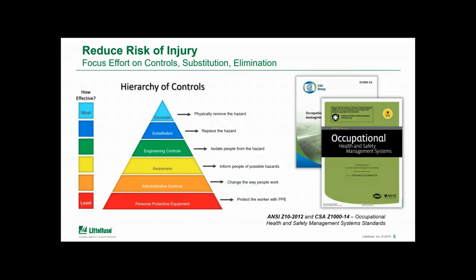Now, I do want to be clear that all those 3 items are critical, they're foundational blocks, and should be part of a safety strategy. But what we want to focus on are some of the more effective ways to make the workplaces safer at the top of the pyramid. And again, those operate in conjunction with the ones at the bottom. So these are engineering controls, which would typically try to limit the fault or the incident energy, substitution, which would replace some of the existing equipment with safer options, or elimination at the very top, which can sometimes be difficult to achieve. It is possible in some scenarios.